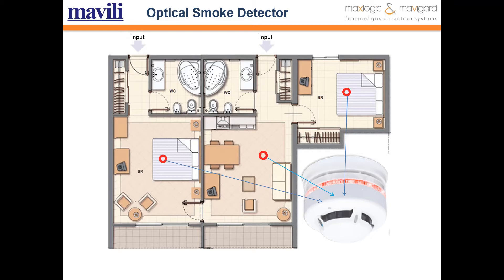Optical smoke detectors are suitable for use in hotel rooms and general areas where there is no moisture or dust. In hotel rooms, the exit areas of bathroom and toilet sections can generally be exposed to water vapor, and false alarms may occur if a detector is placed in these sections. It is therefore ideal to position smoke detectors above the bed area.